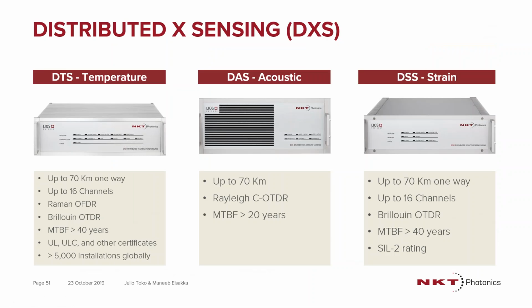Getting into the overview of product offerings, we do more than just linear heat detection systems. We have distributed temperature sensing, distributed acoustic sensing, and strain sensing. The applications are similar and a little bit different, and we have a full portfolio. Temperature sensing is very popular in the power cable world, where we can stretch long distances of 70 kilometers and go up to 16 channels, with a mean time between failures of about 40 years. So we do more than service the fire detection world. We do a lot more monitoring as well.